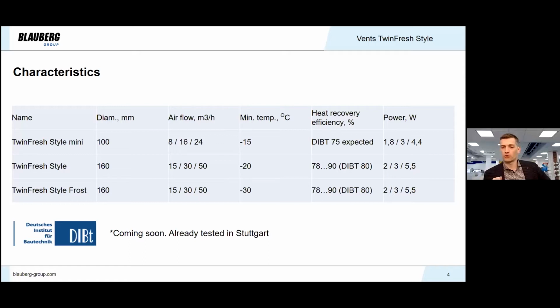Minimum operation temperature of twin fresh style is down to -20, which is good. The unit was already tested in Stuttgart, and we can provide you with a test report on your demand. The twin fresh style did show 80% of heat recovery efficiency according to DIBt, and from 78 to 90 according to EN 13141-8. According to this kind of European norm that is at the moment actual for European Union. Soon we will receive the DIBt certificate for this unit based on the Stuttgart test report.